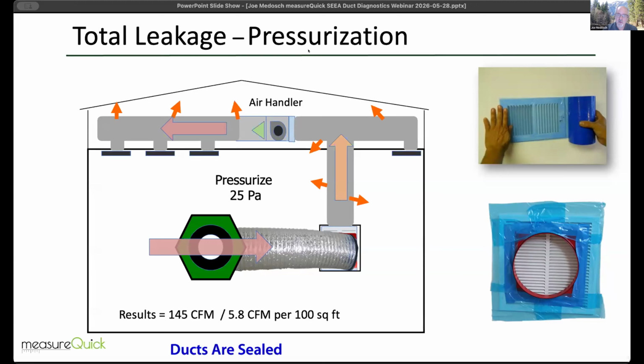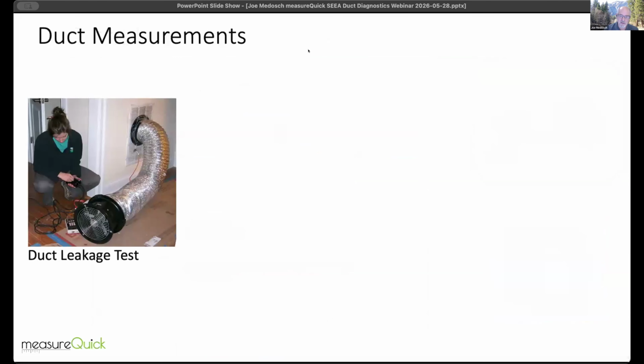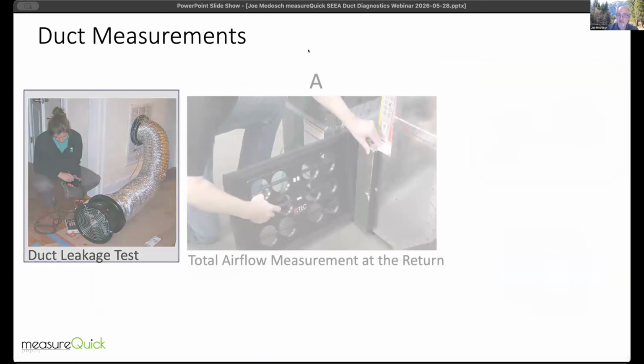So if you're installing ducts, you're using ducts, if ducts are a part of your process that's in your HVAC world and you are not measuring the conditions, then I'll be honest, I kind of say shame on you, because there's so many ways to do this now. The duct tester is clearly the most obvious, but we're now moving into another world where we can use things like the TrueFlow grid and other complementary stuff to kind of confirm, is it performing correctly? And even maybe can I extrapolate, is there potential leakage in this system? So this is our normal duct leakage test, all right? And we're now moving past this and getting into other options.